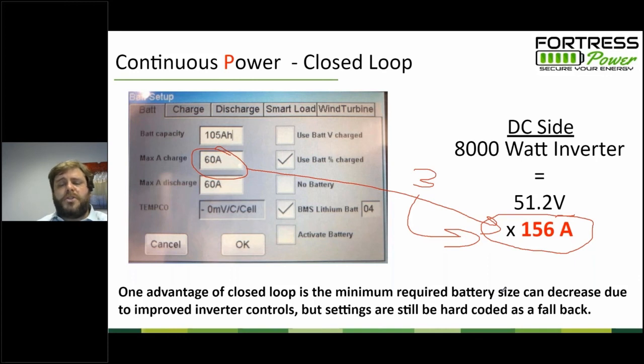The problem is if you don't watch your cell voltages closely during those times, it can result in a lower life for the battery bank. If you read through our product warranties, it shows that if you run the battery in a harder mode of operation, it can diminish the cycle life of the battery. So if you are just taking a random battery off the shelf and a random inverter off the shelf, and you're doing all of the controls based on the battery voltage, and the inverter is reading the battery voltage off the battery terminals and doing its charge and discharge settings based off of that, that's what we call open loop. To some extent, that is less controlled than if the battery has a computer and it talks directly to the inverter.